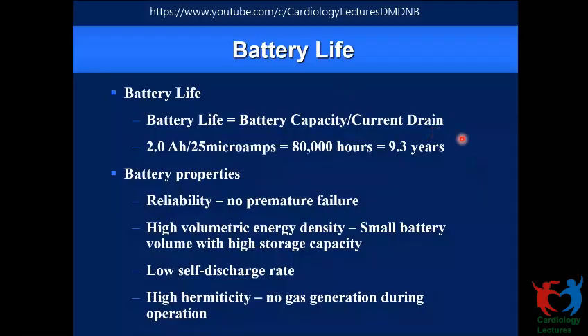And lithium iodine battery is a reasonably good battery. It does not undergo a sudden premature failure, and that's why lithium iodine battery is used today. And in the most recent pacemakers, what is used is actually a battery that is used in ICD. It's lithium silver vanadium oxide, also with an additional compound called carbon monofluoride that makes the battery last a little longer. And typically that is used in an ICD because you need high power, or high current, to be suddenly drained when the device needs to deliver a shock.